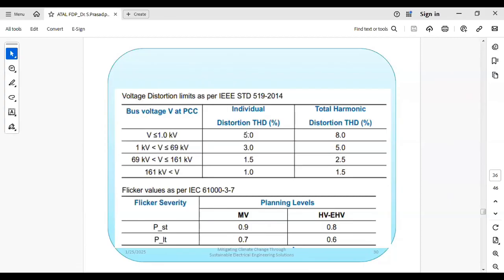And for the source you are using, in the original OEM data sheet you will get the harmonics report of the solar inverter. You have to use it as input data to find the total harmonics injected at the point of interconnection. Therefore, you must have the original equipment manufacturer data sheet while simulating the SLD in ETAP or DIgSILENT PowerFactory software. That is the most important point. Whenever you purchase an inverter, the data sheet will specify the harmonics test report you should have, and you will get it from the OEM data sheet.